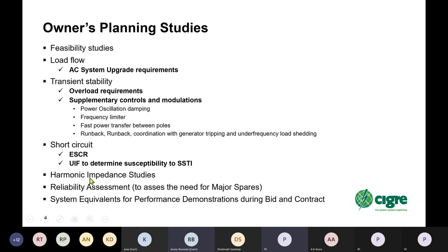Harmonic impedance studies, for obvious reasons, are needed for filter design, and reliability assessment to assess the need primarily for major spares in the HVDC. With the reliability assessment, you can decide whether or not it makes economic advantage to buy major spares or to accept the outage as a consequence of not having the spare.